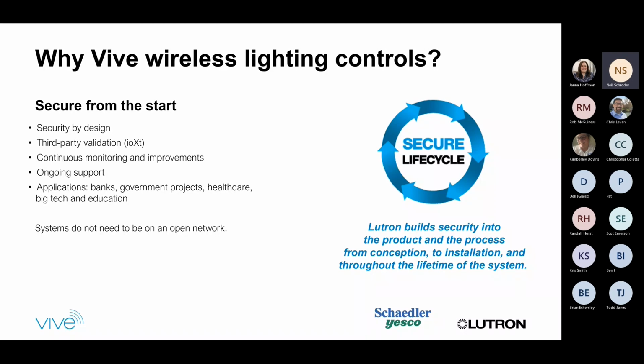We can integrate with fire alarm via contact closure. We'd have some device monitoring a contact closure, or if your fire alarm system has a contact closure output, we can take that straight into the back of the Vive hub, and trigger light levels based on a closure opening, set up as normally open or normally closed, maintained typically contact closures. So we can monitor that and trigger lights based on the fire alarm being triggered. Great question, thank you.